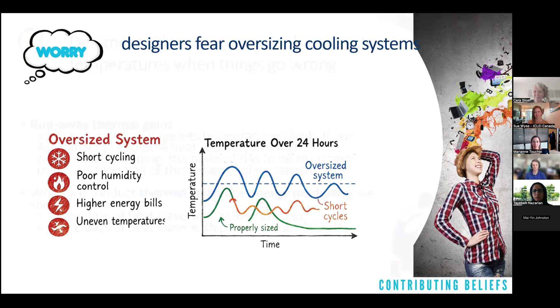And that speaks to my next point, which was that I didn't really think about what happens when things go wrong. And the specific thing I didn't imagine going wrong was that I have an energy recovery ventilator that covered 80 to 85% of my cooling capacity. So the air coming back from the building should be 24 degrees Celsius. So we're going to do energy exchange. We'll take our 35-degree air, we'll get it down to 26C. So my coil only needed to do the last 2 degrees.